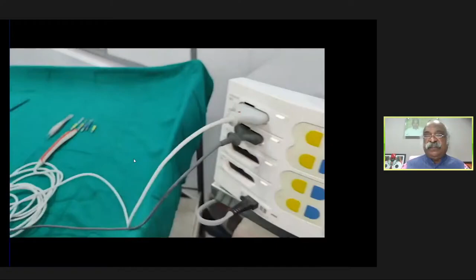Now, what is a bipolar? The active and dispersive return electrode are components of the same instrument. The body is bypassed. You catch with the instrument, there is an active, and it catches the tissues, and then through the other portion of the electrode, it comes back. Current density is identical at both the electrodes, in contrast to the monopolar, where there is a difference in the current at the active and the dispersive electrode. And only the tissue grasped by the electrode is the part of the body that is involved.